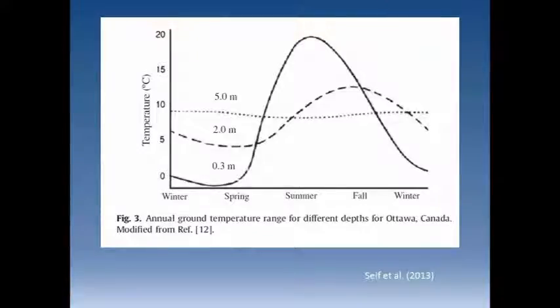Ground source geothermal heat pumps take advantage of the temperature difference between the ground at not too great a depth and the surface. This graph is for Ottawa, Ontario, and shows soil temperatures at 3 different depths: about 1 foot, 2 meters, and 5 meters. As expected, the shallowest one has the widest swing in temperature, about 20 degrees between winter and summer. It's damped out quite a bit at 2 meters, and at 5 meters there's hardly any change at all.